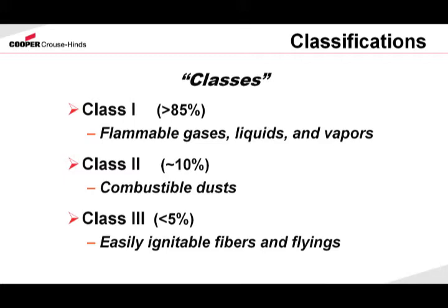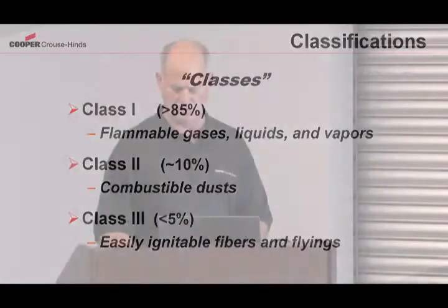Examples of these: in Class 1, flammable gases and vapors — refining applications, chemical plants, wastewater treatment plants. Class 2 locations would be grain elevators or flour mills. A Class 3 location — flyings and fibers — would be found in a textile mill or a cotton gin.